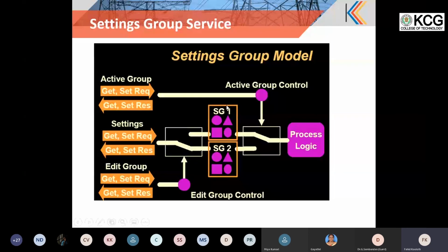For example, if your frequency goes below 49 and you want SG1 to be activated, you change from SG2 to SG1 using the setting group control command. Then if you want to edit SG3, you copy SG3 to the edit setting group, make edits of the parameters, and apply. Then SG3 is available now. Once it needs to be triggered, switch to SG3 so that SG3 goes into the active setting group. So this is one of the models available. If a vendor supports a setting group function, many IEDs need a group of settings applied based upon different conditions, and the setting group model will be used.